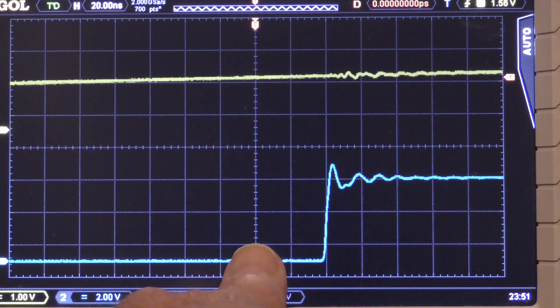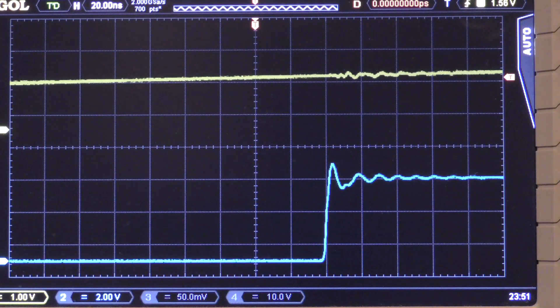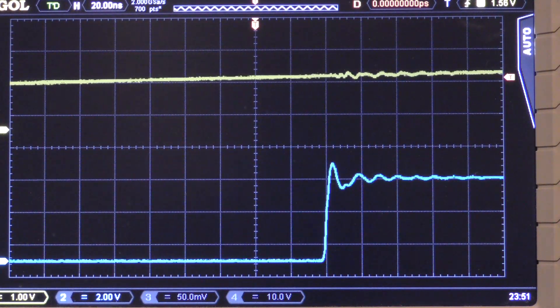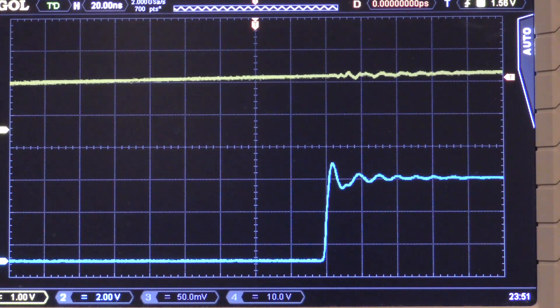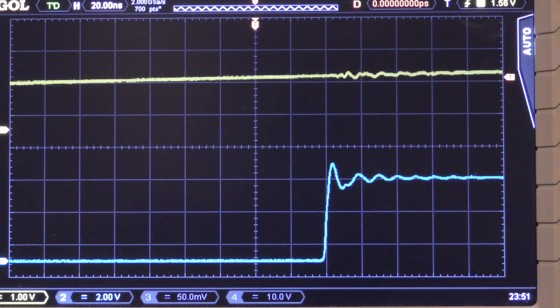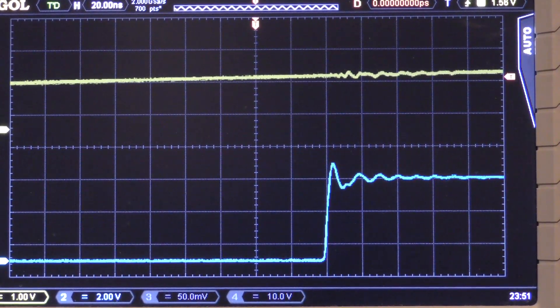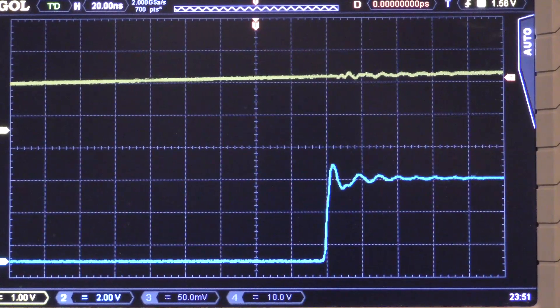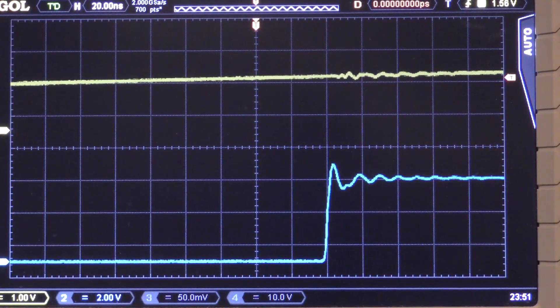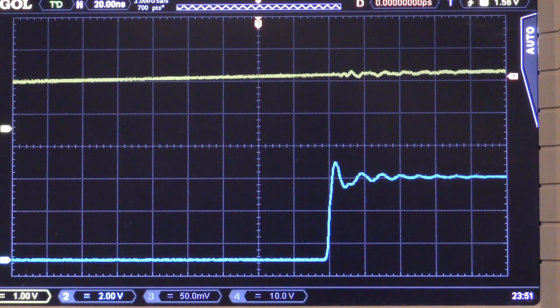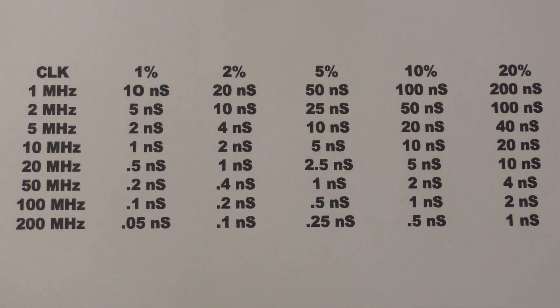Remember that we're looking for something where the errors, if you will, in the measurements are down in the single digit percentages of the clock pulse itself. So, let's take a look at some of those values and you can kind of get an idea of how much you can tolerate between these two and still use the trigger out with an external instrument.